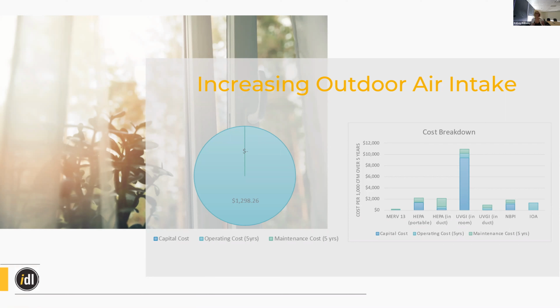So that's why we didn't include maintenance costs, because you wouldn't really increase your outdoor air long term if it was a non-DOAS system. But do know that if you had to, like we all did at the beginning of the pandemic, when we were like, we can't be breathing this nasty air, then there is probably going to be some maintenance associated with that wear and tear. But really just high operating costs, just because it takes so much energy to condition the air and then make it suitable for your temperature and humidity set points.